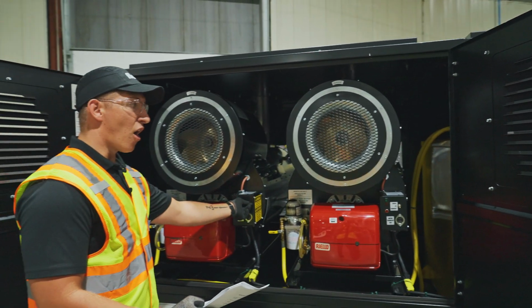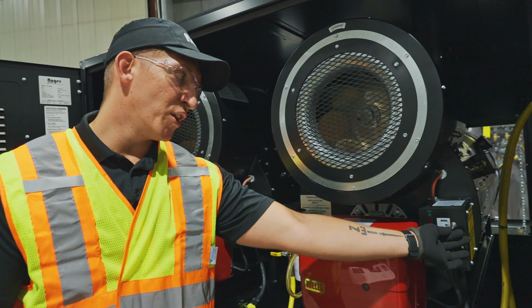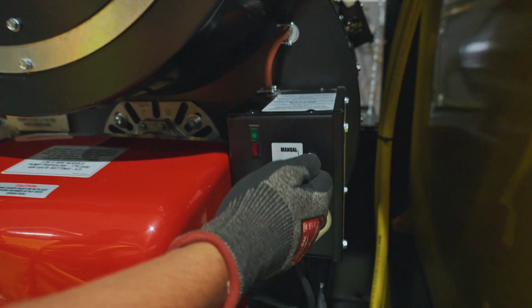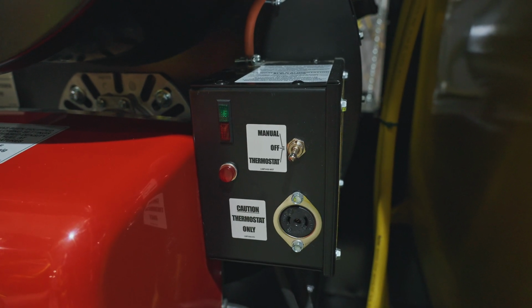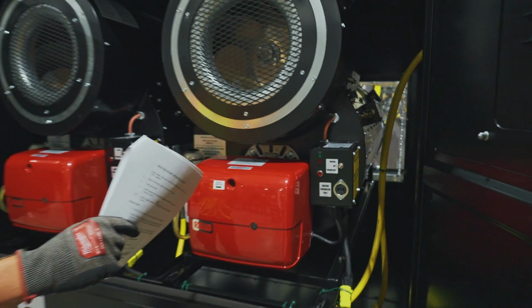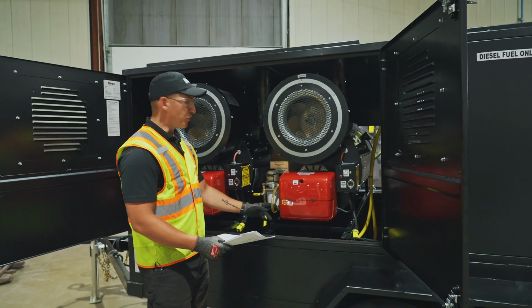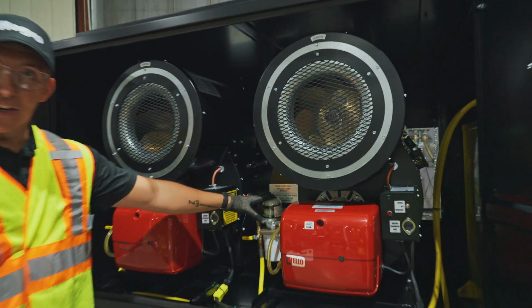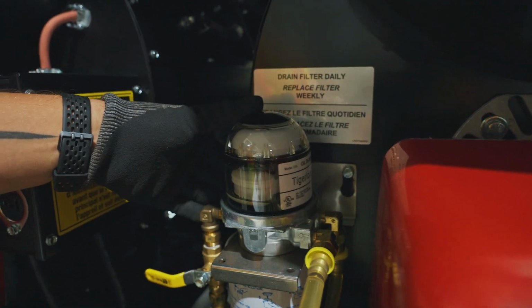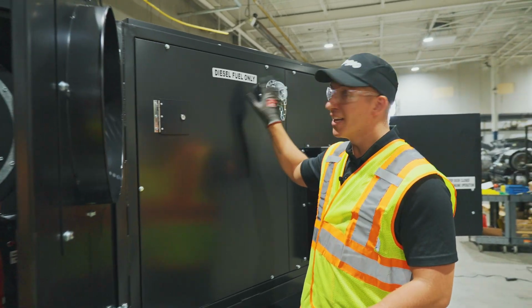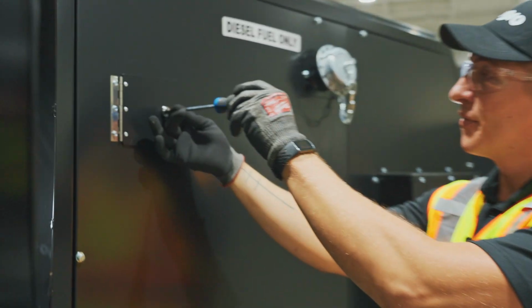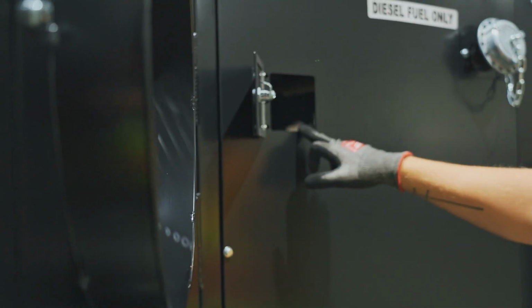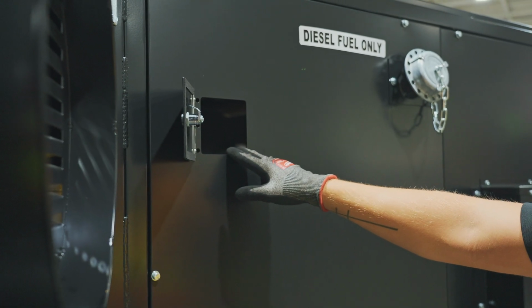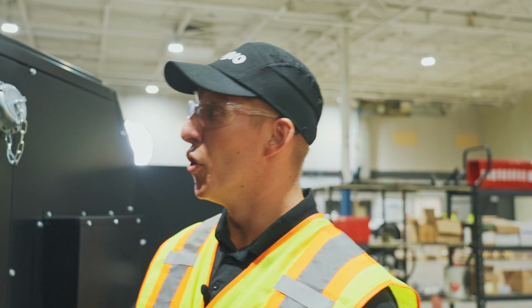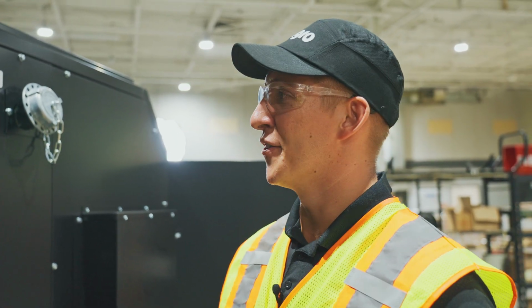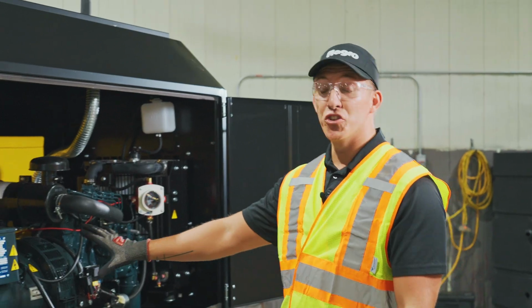You want to make sure these are set in the off position before you start. So you've got a manual, an off, and a thermostat. And you'll want that in the center on off there. Give a quick visual inspection of the heaters themselves. Make sure you got no air in your fuel lines. Make sure your filters are clear on the Tiger Loop system. There's a small door on your fuel inlet side. You use a flathead screwdriver to open this door, and that's a window into your fuel gauge on your diesel tank. You want to make sure your fuel is full before you attempt to run these heaters, or they're not going to start. So if everything meets specifications, you're ready to turn your genset on.